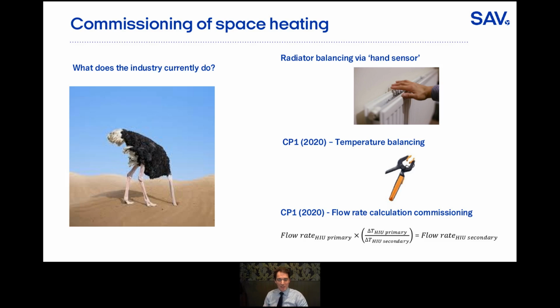The difficulty we have here is it takes a long time, you have to wait for it to stabilize, and then also you get into the issues of what happens in summer when the room temperatures are too hot and you cannot get that design criteria and that low return temperature to verify it's been set up and commissioned properly.